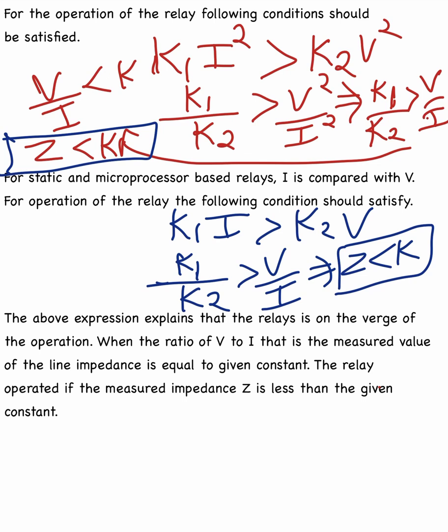In summary, the impedance relay measures the impedance of the line at the relay location. When a fault occurs on the protected line section, the measured impedance is the impedance of the line section between the relay location and the point of fault. This is a key answer for impedance relay questions in interviews.